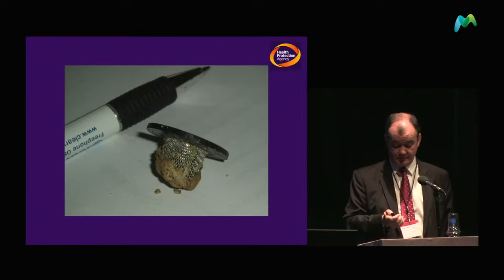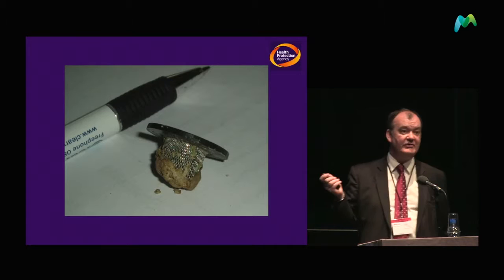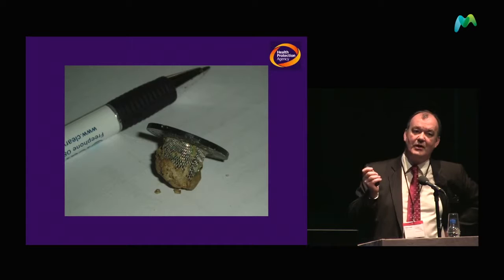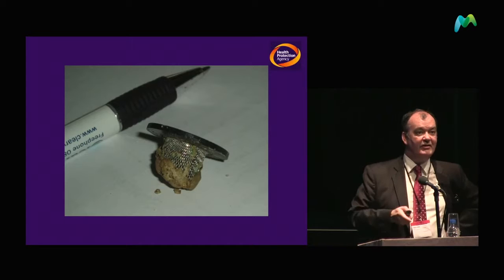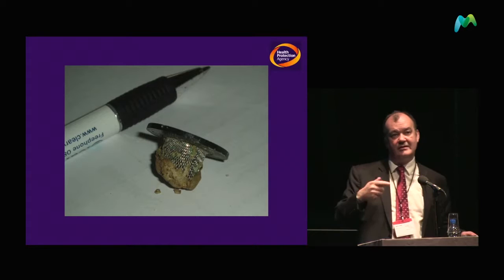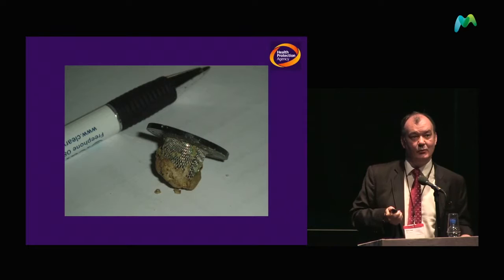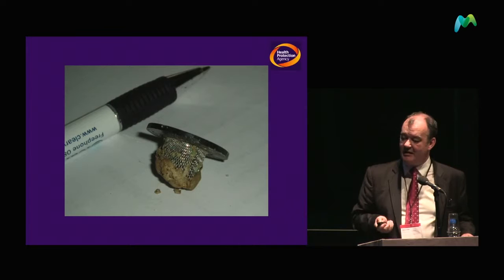That's a filter from a TMV valve with a biofilm, taken from a hot water tap in a hospital where they were having recurrent problems with Legionella from that particular tap. It was retrieved in situ from a sink filter in one of the wards, representing a build-up of biofilm — the sort of thing that presents a real problem in trying to track down within a water system exactly what the problem is and the remediation required.